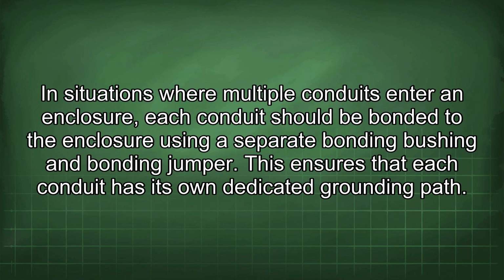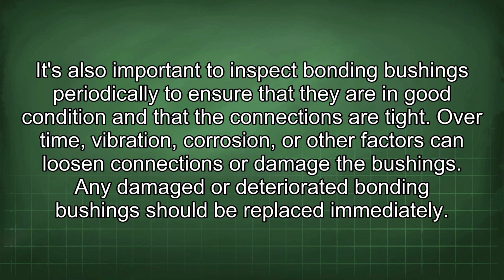In situations where multiple conduits enter an enclosure, each conduit should be bonded to the enclosure using a separate bonding bushing and bonding jumper. This ensures that each conduit has its own dedicated grounding path. It's also important to inspect bonding bushings periodically to ensure that they are in good condition and that the connections are tight. Over time, vibration, corrosion, or other factors can loosen connections or damage the bushings. Any damaged or deteriorated bonding bushings should be replaced immediately.